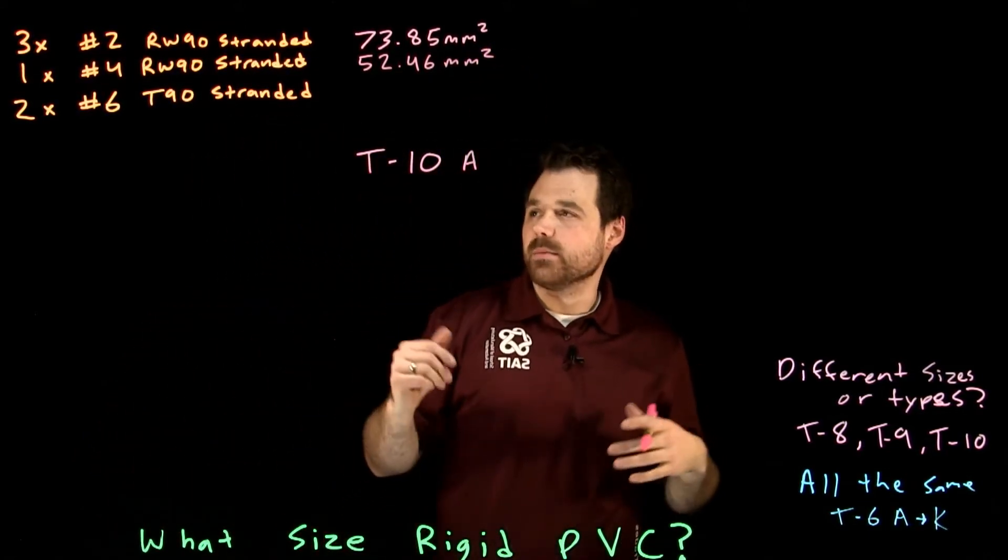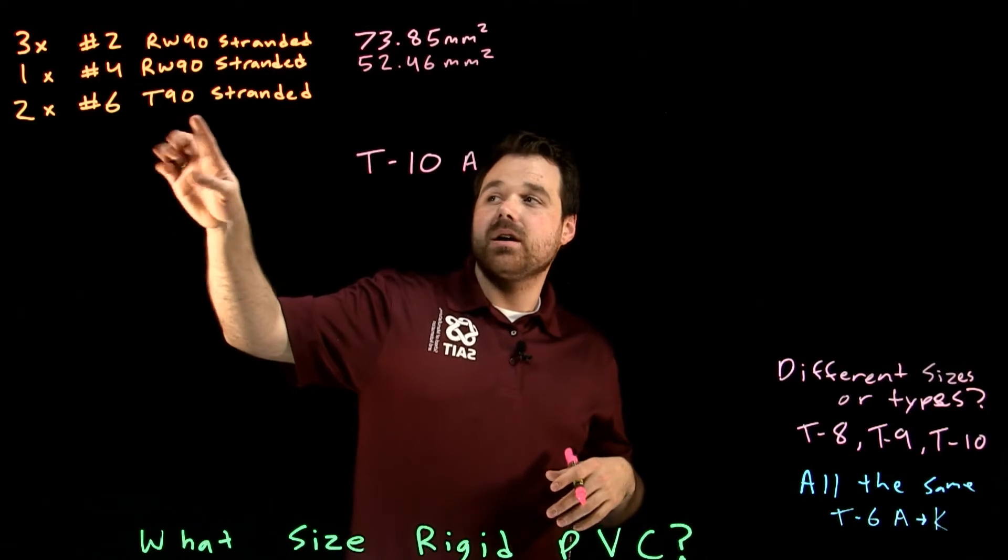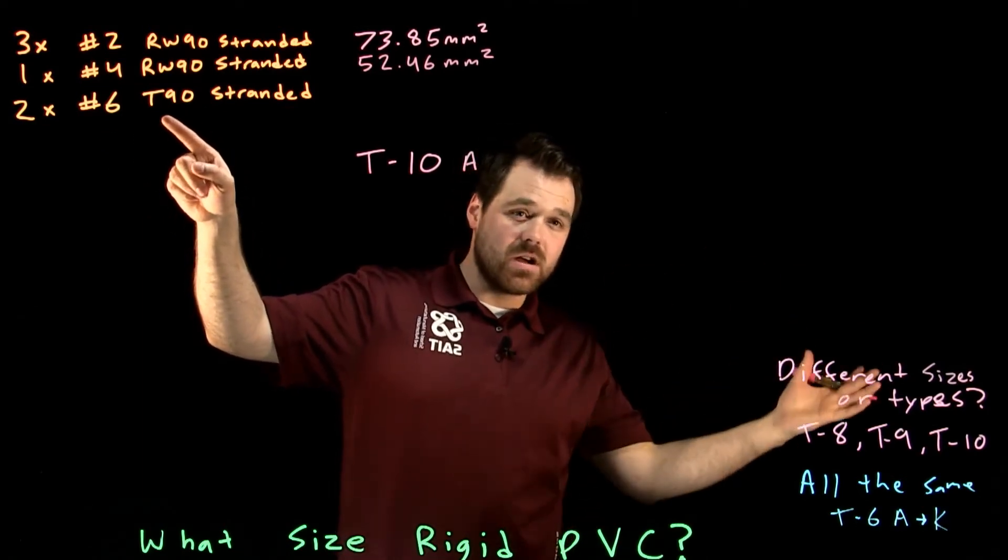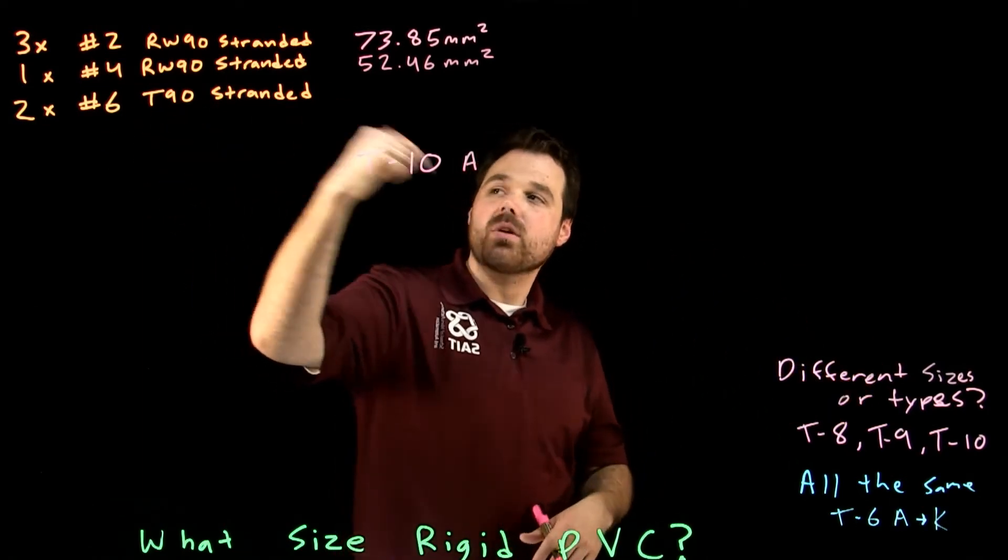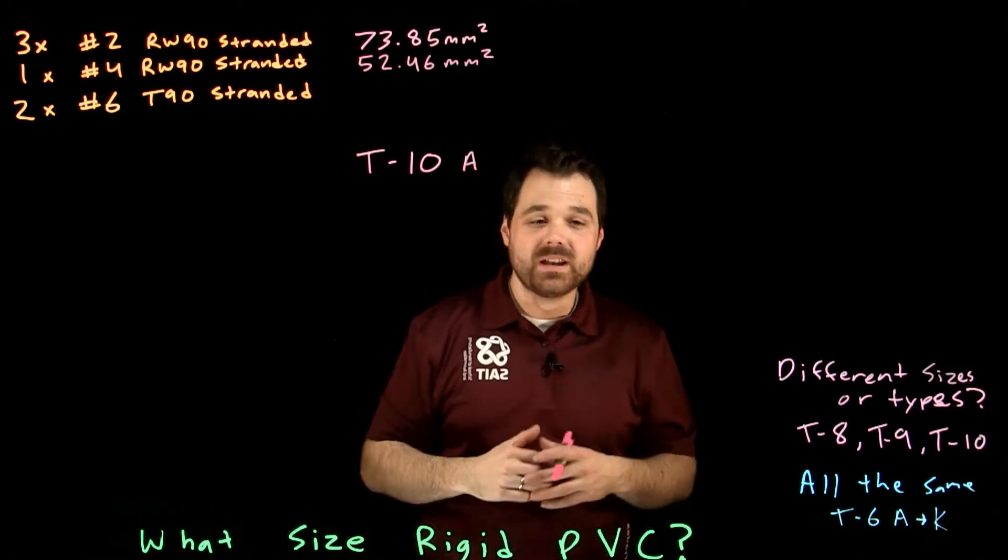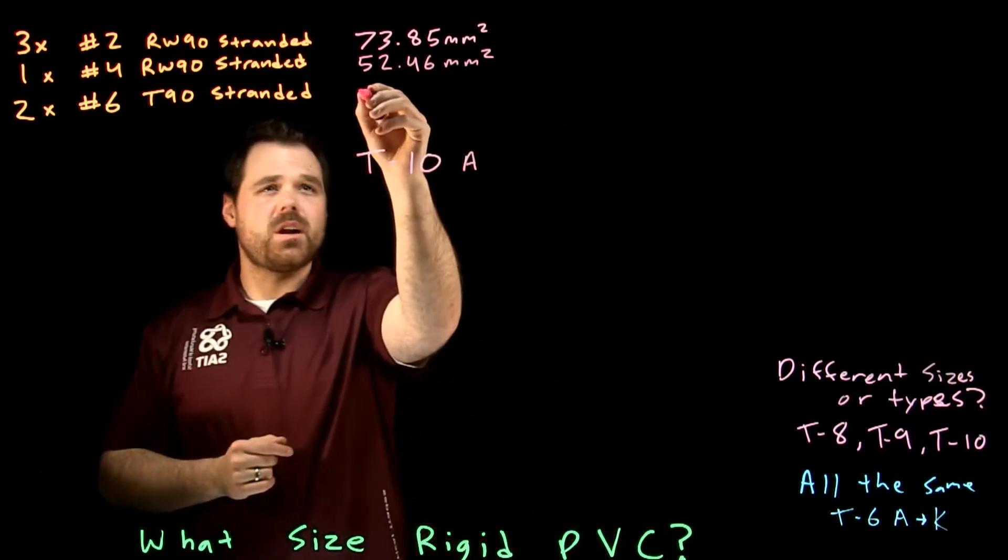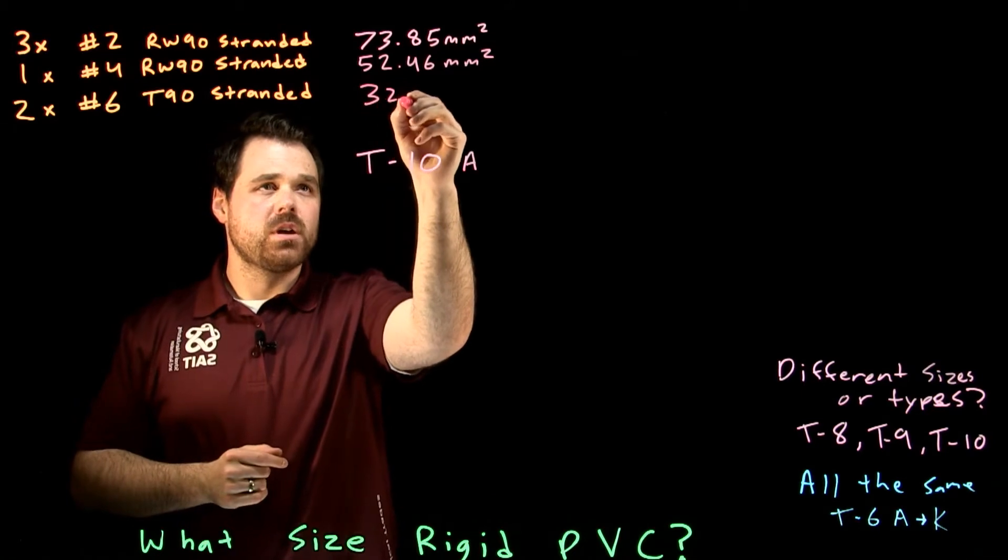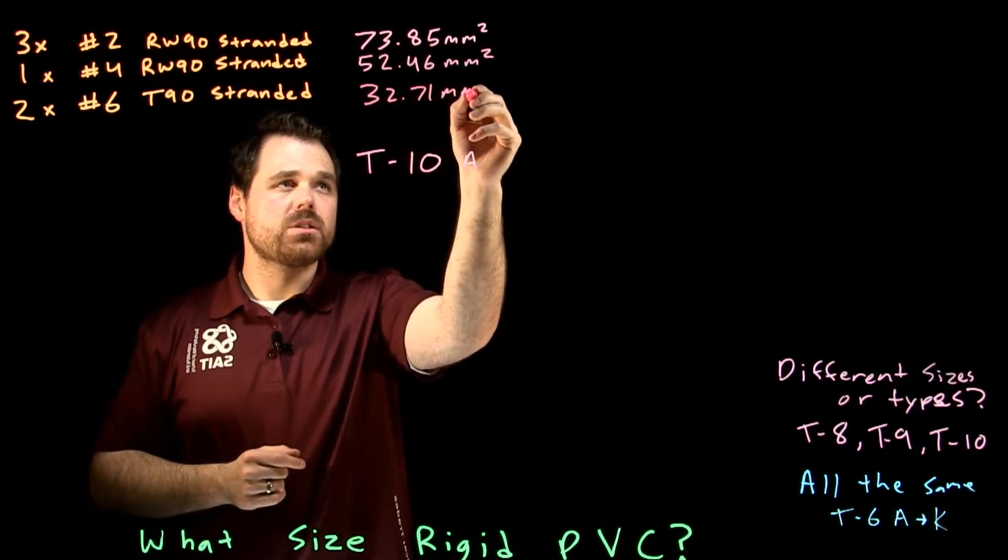Then we go back. Table ten A, number six. Now we're paying attention. The T90 is actually not in the first column anymore. We're going to go over to the column that's for T90, number six, which tells us they are each good for thirty two point seven one millimeters squared.